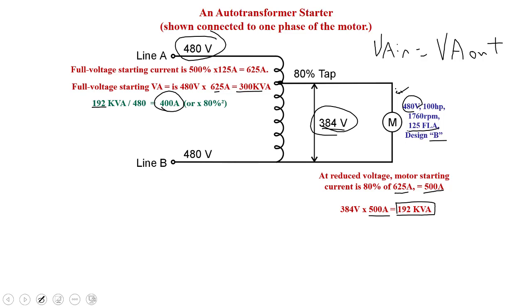If you want to know the current at the motor, the I of the motor during reduced voltage starting, you take your I full voltage starting calculation, I FVS, and multiply it by your percent tap. In your ILM, it refers to this as your reduced voltage over your full voltage. It's really just your percentage. So the I of the motor during reduced voltage is I full voltage start times your percent tap. If I want to know the I going to the line side of my auto transformer during a reduced voltage start, we take our I full voltage start and multiply it by our percent tap squared.